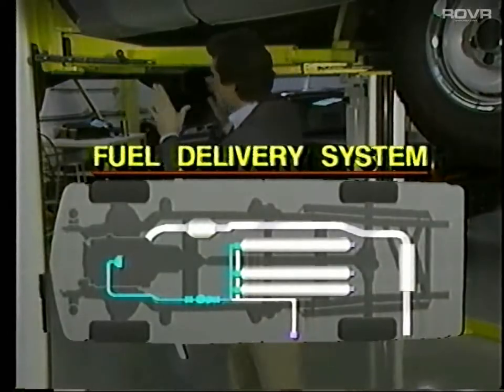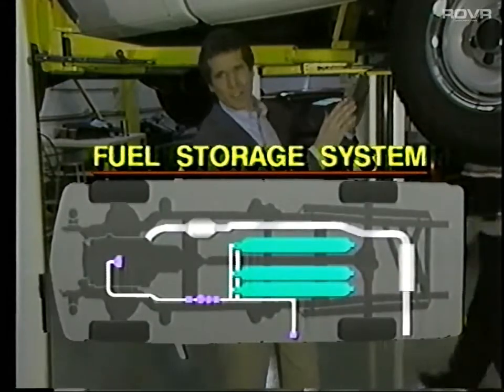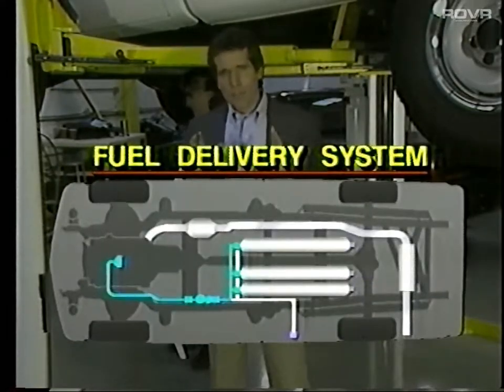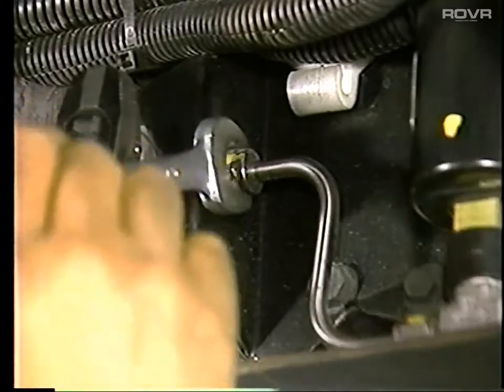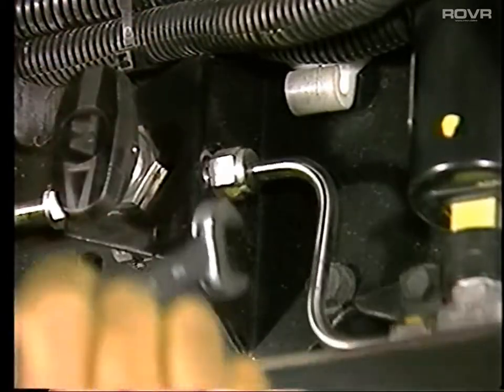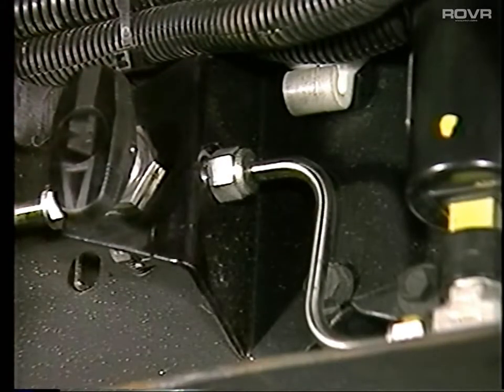For venting purposes, think of the system as being made up of two separate systems, the fuel delivery system and the fuel storage system. Let's discuss venting the fuel delivery system first. If you're venting at an inline component, use an open-end wrench. Crack the seal and slowly turn the nut one full turn to let the fuel slowly escape. If you unscrew the nut entirely while the system still has pressure, the pressure can cause the disconnected line to flail. This can happen on both the high and low pressure sides of the system.